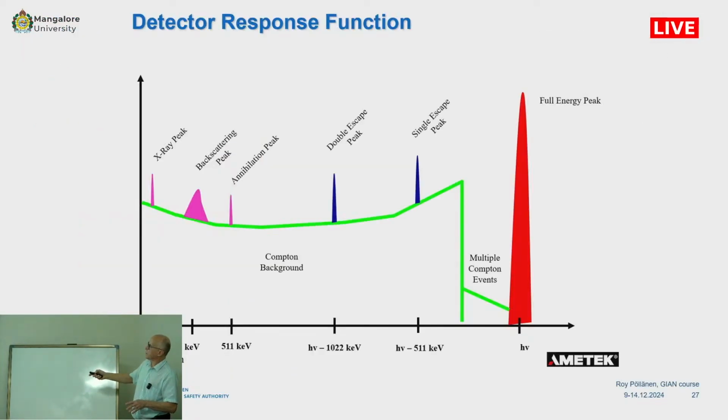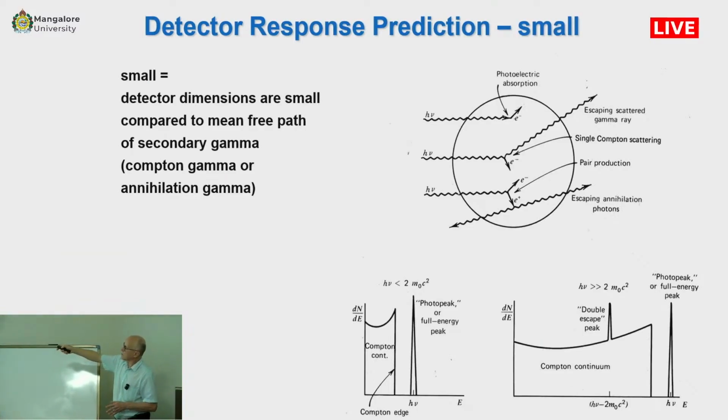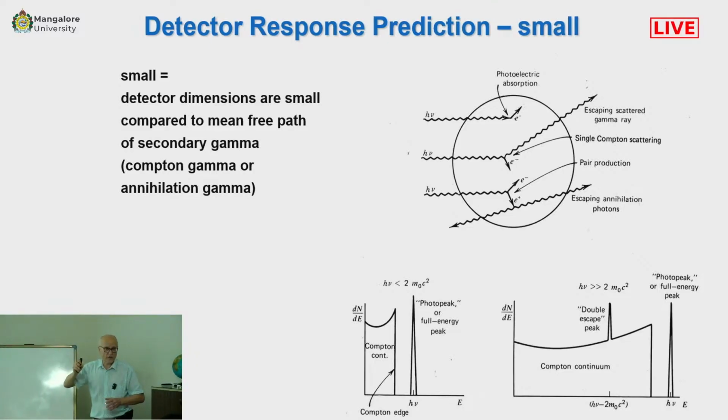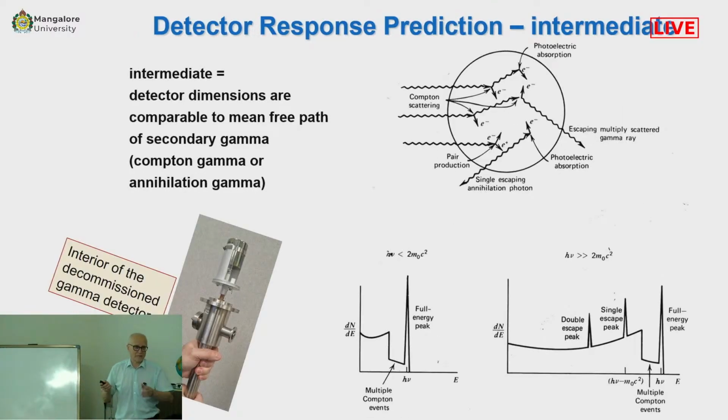If this interaction happens very close to the surface of the detector, it might happen that this K electron goes out of the detector. So there is an energy loss, and in fact, because the americium energy is so low, interactions mainly happen close to the detector surface. So it's a germanium escape peak.